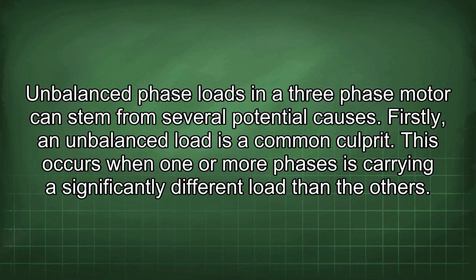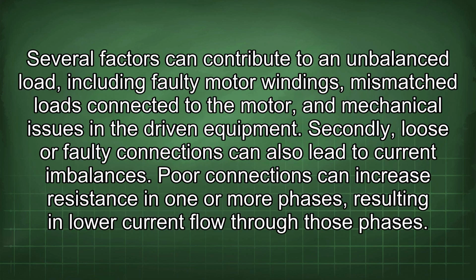Unbalanced phase loads in a three-phase motor can stem from several potential causes. Firstly, an unbalanced load is a common culprit. This occurs when one or more phases is carrying a significantly different load than the others. Several factors can contribute to an unbalanced load, including faulty motor windings, mismatched loads connected to the motor, and mechanical issues in the driven equipment.